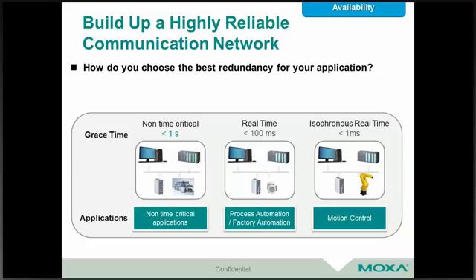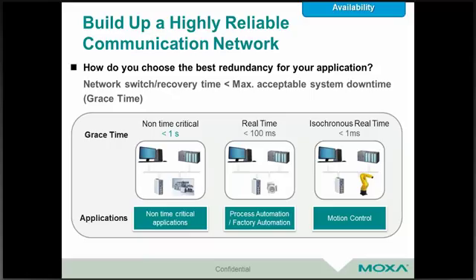We move then into real-time, and real-time redundancy is what's typically classified as less than 100 milliseconds. This is very common in factory environments for process or factory automation. These applications do have a little bit of flexibility in terms of recovery time, but that's typically no longer than 100 milliseconds. Finally, the isochronous real-time, which is less than 1 millisecond, is for extremely mission-critical applications like motion control. So if you can't afford any kind of downtime, this is the type of redundancy you're going to want to look at for your network. Typically, what we recommend is that the network switch recovery time be less than your maximum acceptable system downtime. We also call this grace time.